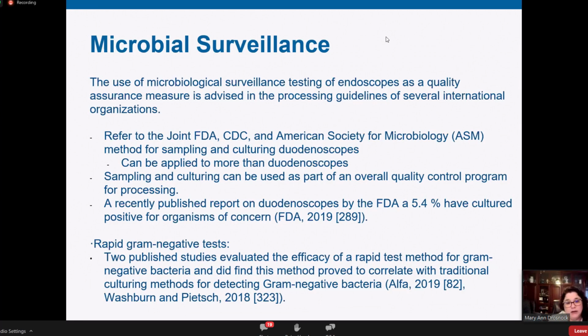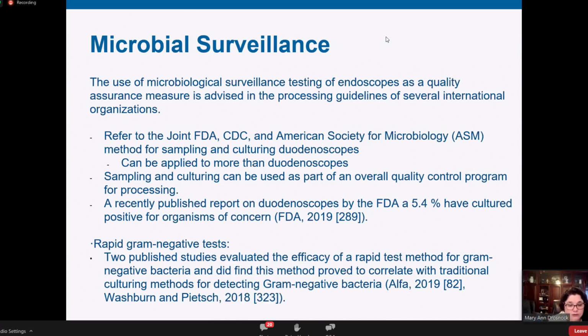And I believe since then there have been more results published from the FDA. So we do have recommendations from the FDA to do more with these types of scopes, your duodenoscopes in particular. Sterilization is one thing. Culturing is another recommendation. Liquid chemical sterilization. It used to be 2 rounds of high-level disinfection, but you'll see in the latest recommendations from the FDA that is no longer mentioned. They do that because there's data that shows it didn't matter. You don't get a statistically significant difference whether you run it one time through high-level disinfection in an AER or twice. So think about, what am I doing with my duodenoscopes?